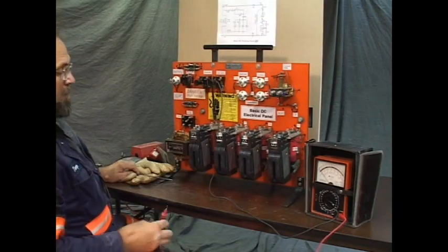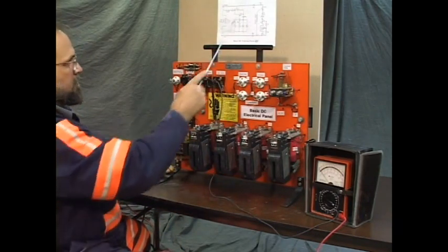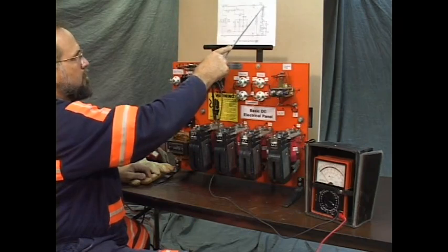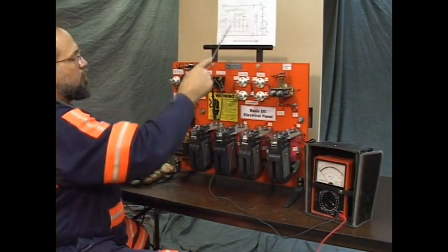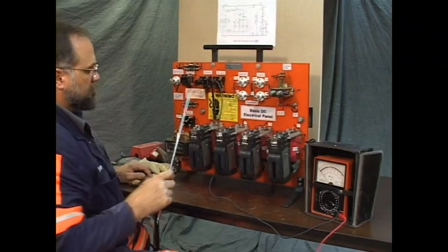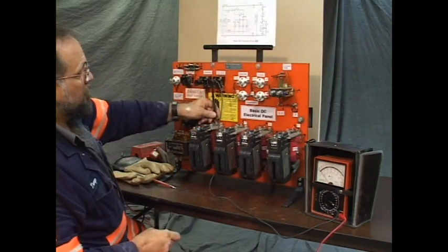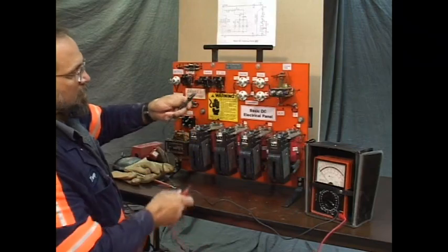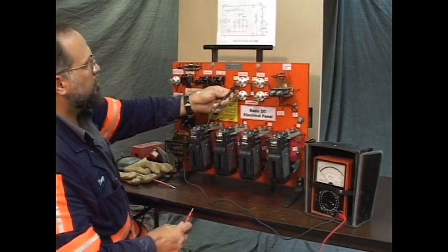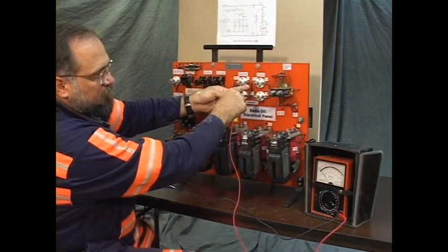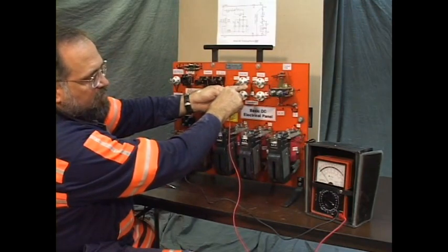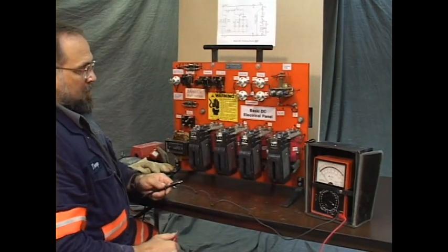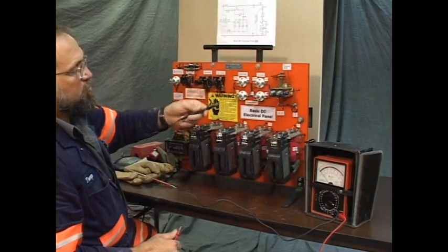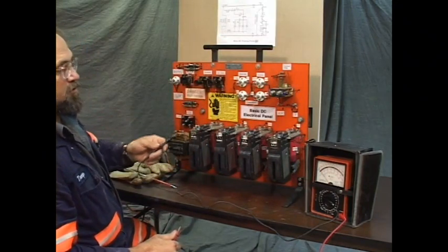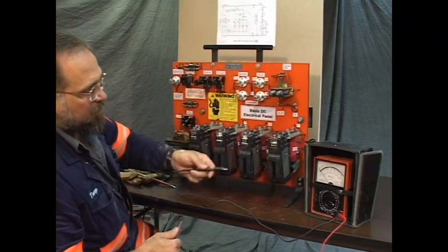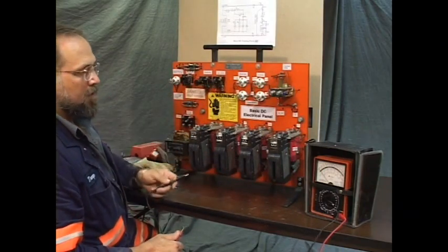Now, at that time, if you reach there, you've checked as far as you can go without reading through one of these light bulbs. And we could read through the light bulb. Watch the meter. When I'm going to read through this light bulb, note the extremely high resistance. Now, that could give you a distorted reading on the control wiring, which should be no resistance.